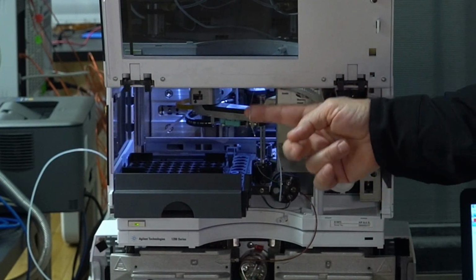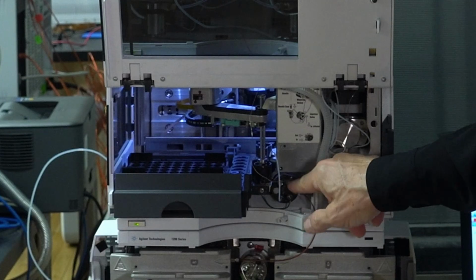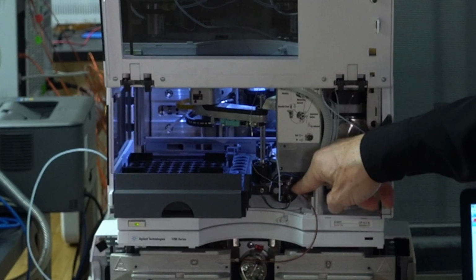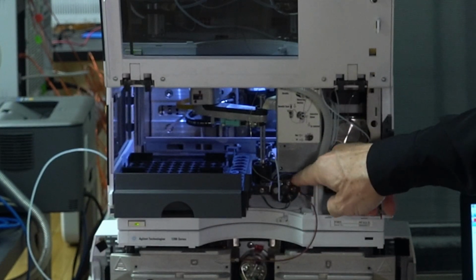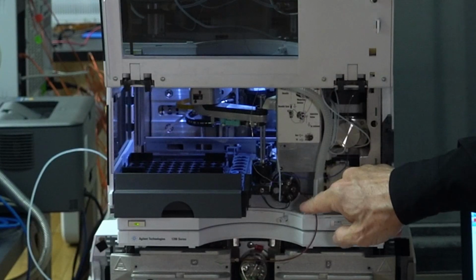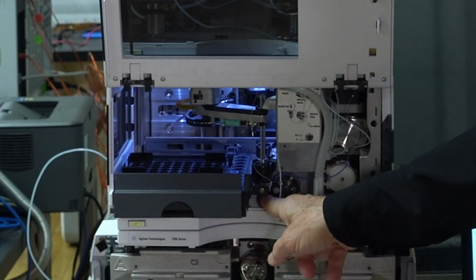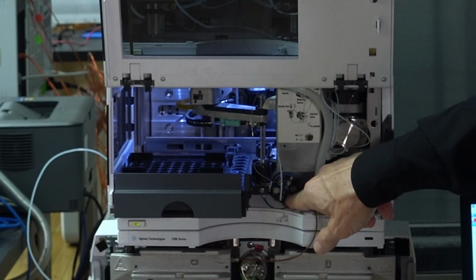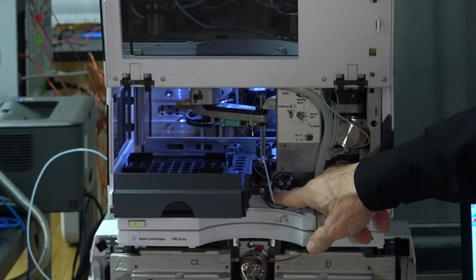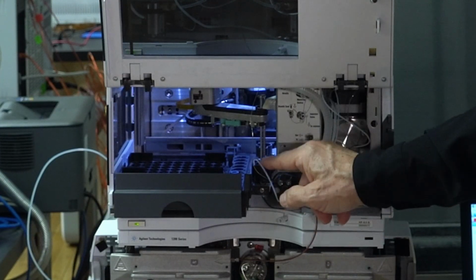Well, we know this is high pressure flow coming in, so that's flow coming from the pump, which means that's going to the column, which means the other side is going to the autosampler. So one of these must be coming back from the autosampler, right? So that's the needle seat coming back in.